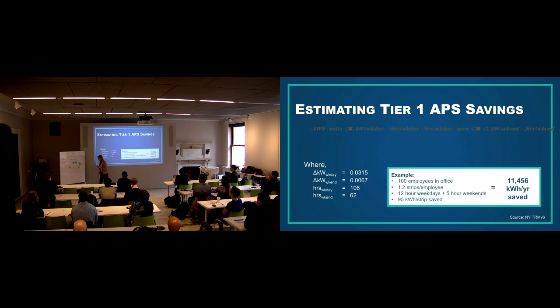All right, sorry about that. So this algorithm is provided by the New York TRM, which is a great resource that provides deemed savings algorithms for a wide variety of measures. This is a great resource for estimating potential savings. So this equation is provided, and the only variables that you need to input are these two that I have underlined here. The remainder are recommended in the algorithm itself: hours open on the weekdays and the count of hours open on the weekends.